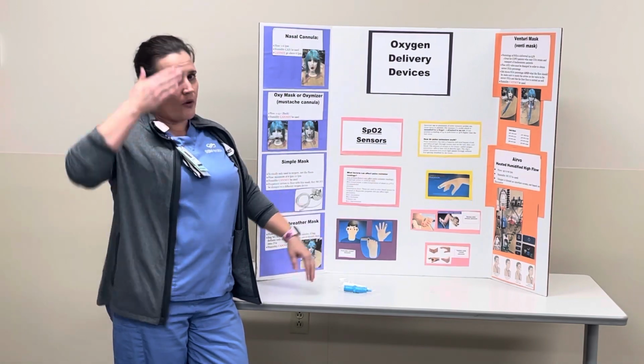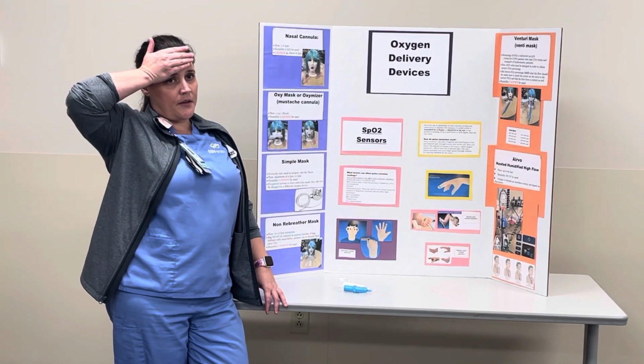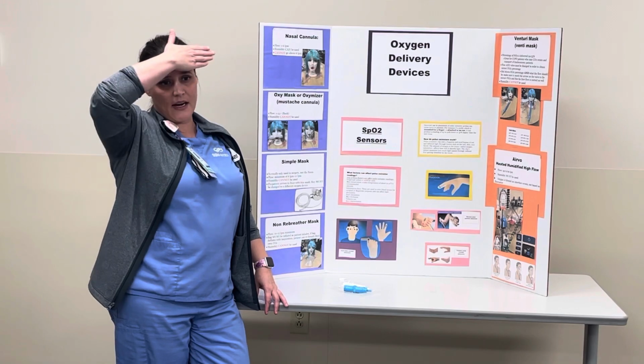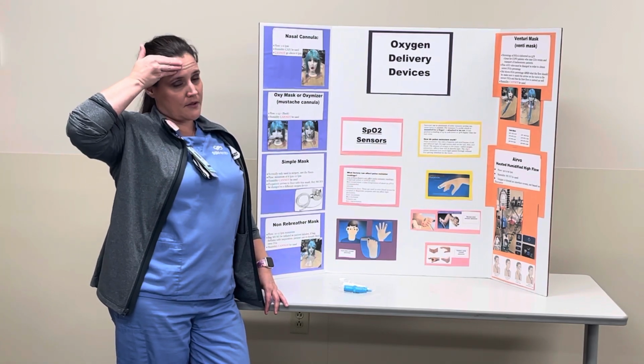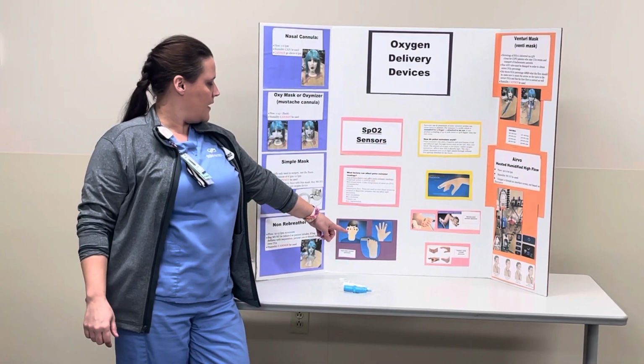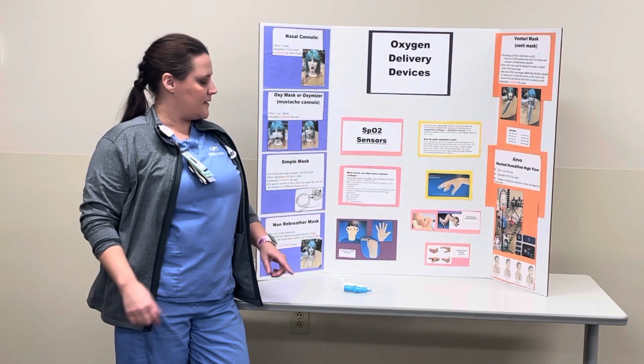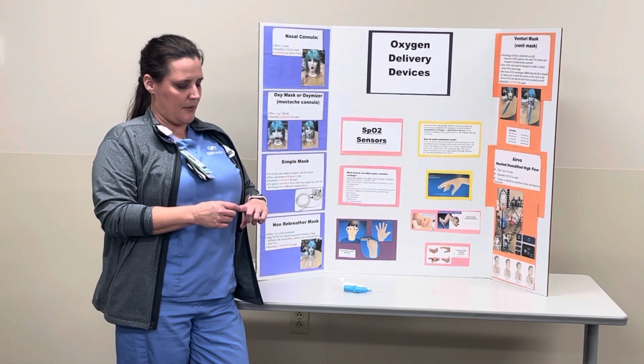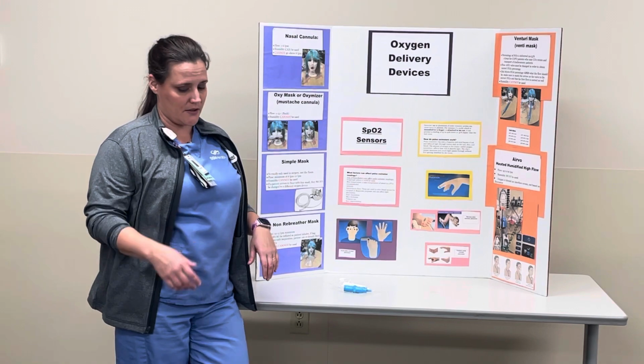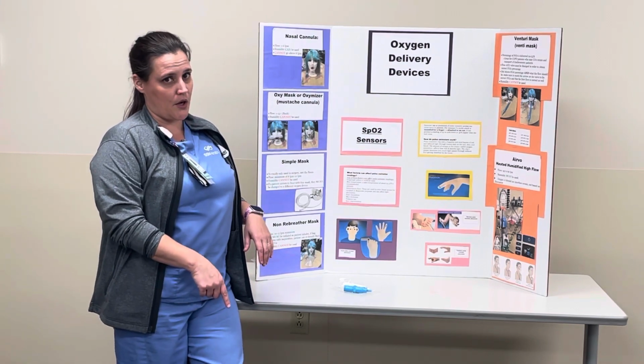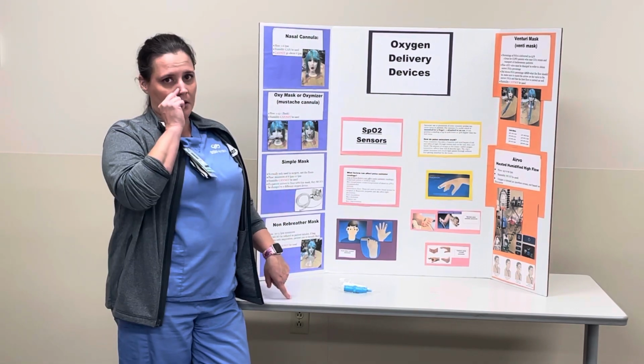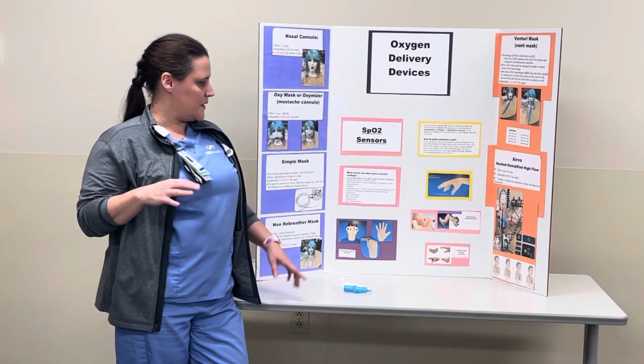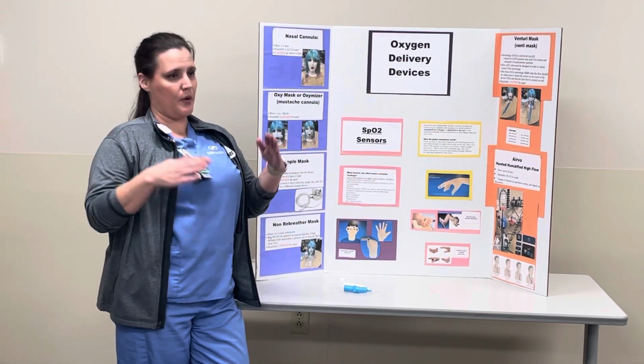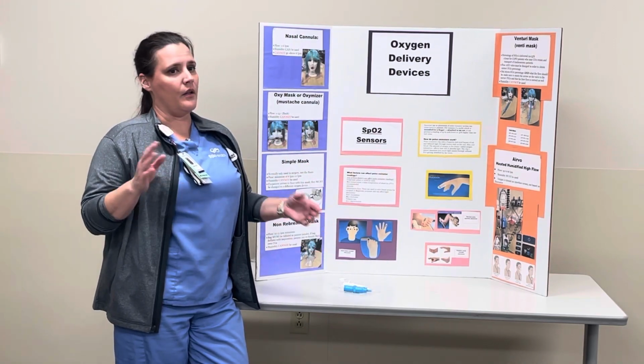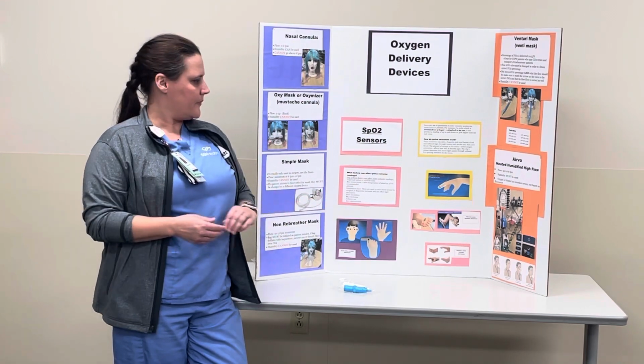You can use a forehead probe. Forehead probe gets placed on the forehead. It has to be moved every 8 hours, otherwise it can cause burns. We have infant pulse oxes for children, pediatrics, sometimes that can work on our patients. You can also use it on their big toes. We have nasal probes and we have ear probes, so just make sure you're using the appropriate probe for the appropriate body part, otherwise you're not getting an accurate signal.